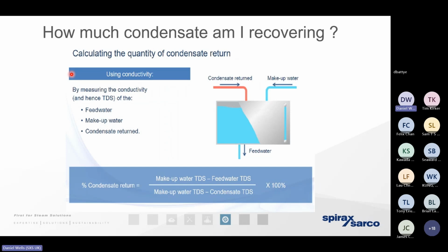So the simple reason is that condensate has already been chemically conditioned. So it's in a fantastic condition for going straight back into the boiler without the need for us to add any further chemicals to it. So the first thing we want to do is to calculate that percentage. For example, if our client is generating 10,000 kilograms of steam per hour, and we've calculated that percentage at 60%, it tells us that we've got 4,000 kilograms per hour of condensate that's going missing somewhere. The question is, where is it going missing?